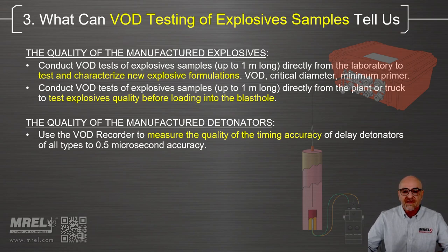With MREL's recorders, you can test and characterize new explosive formulations by testing samples of explosives. You can also be very proactive and test samples taken off the truck before the truck is allowed to load onto the shot. Finally, you can also test the quality of manufactured detonators to measure their timing accuracy, all within 0.5 microsecond accuracy—that's half a microsecond.